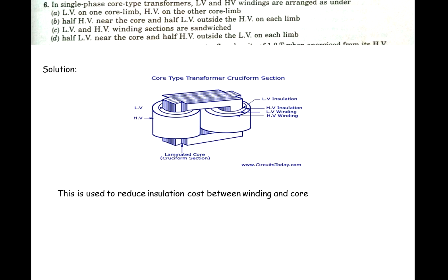If we place HV winding near the core, the insulation required between HV and LV windings due to the large potential difference would be very high and costly. By placing LV winding near the core, the insulation between LV winding and core is reduced, and the potential difference between LV and HV windings is also reduced. So both insulations — between HV and LV, and between LV and core — are reduced in this arrangement. Option D is correct.